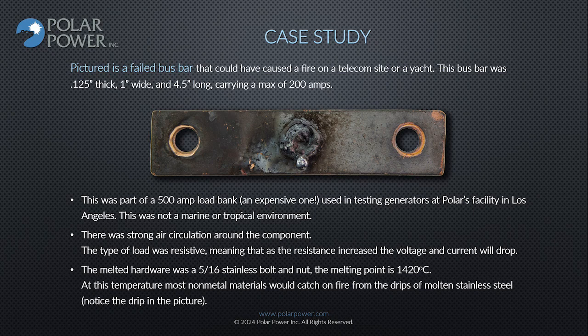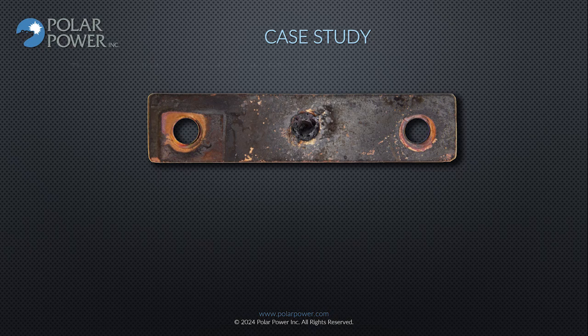The type of load was resistive, meaning that as the resistance increased, the voltage and current will drop. The melted hardware was a 5/16 stainless bolt and nut. The melting point is 1420 degrees Celsius. At this temperature, most non-metal materials would catch on fire from the drips of molten stainless steel. Notice the drip in the picture. There were multiple causes leading to the failure of this part.